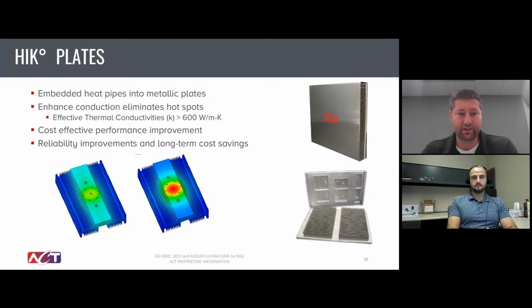An example of that, as you see on the bottom left figure, is a single metallic IGBT cooler. A single IGBT was mounted to those systems. In this thermal model, we used the inputs on both the left and right. The right one was the pure aluminum, and the left one was after it was integrated with heat pipes. And you can see the hotspot elimination there. The heat pipes, with that 2 to 5 degree temperature gradient along the length of the pipe, will spread that heat to the extremes of the heat sink. So not only are you eliminating the hotspot and reducing the case temperature of your electronics, but you're getting better fin efficiency from the outer fins in that scenario. That's one example that you can see there from a thermal analysis standpoint.